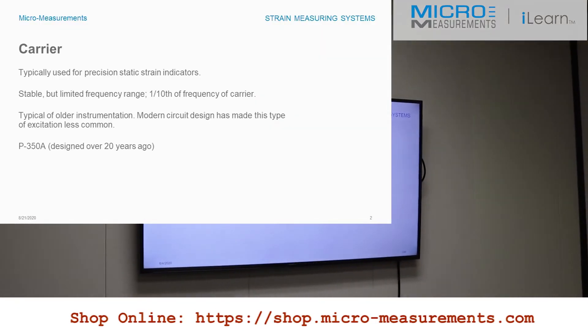In fact, Vishay Nobel makes a product that has millivolt per volt to eight decimal places — very, very stable. Carrier excitation is typically used in the development of transducers these days, where you need very accurate and stable readings. One of the limitations is frequency response: the frequency of the carrier has to be ten times that of the signal, or you're going to attenuate the signal as you're modulating it out. It's very typical of older instrumentation. The old P350, discontinued for 35 years now, used carrier excitation. Very rarely used anymore.